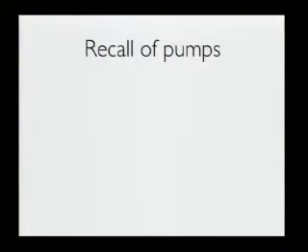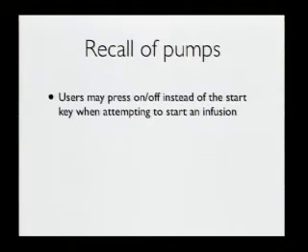Baxter made some pumps, and just to give you an idea of the scale of the problems, the users might press on-off instead of the start key when attempting to start an infusion. And I'm not surprised about it. I've been in a number of operations, and it's very common for anaesthetists to get into trouble and switch the gadgets off and on again to reset them.